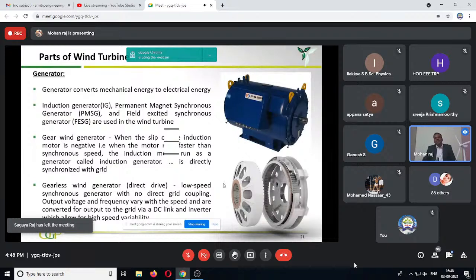And the next is the generator. The generator converts mechanical energy to electrical energy. As I said, the induction generator is the most popular in wind turbines. 80% use induction generators. Another one is the permanent magnet synchronous generator. This permanent magnet synchronous generator is used for the direct drive turbine, so the rotor is directly connected to the wind turbine. And the third one is the field excited synchronous generator. The rotor has the field winding, which gives the excitation. Excitation power is required for generating the power. In a permanent magnet generator, it is not necessary to give excitation.